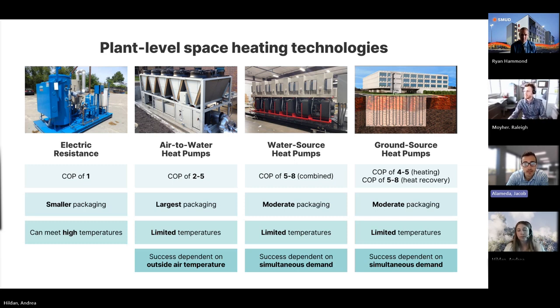But there are a lot of different types of air-to-water heat pumps. To start, they can be modular or packaged. Modular units typically have a little bit better turn down. Each module typically has multiple compressors, and the modules can stage on and off as demand goes up and down. A packaged unit is more like a traditional air-cooled chiller. It typically has a couple of compressors. They can stage on and off, or they could be variable speed compressors as well.